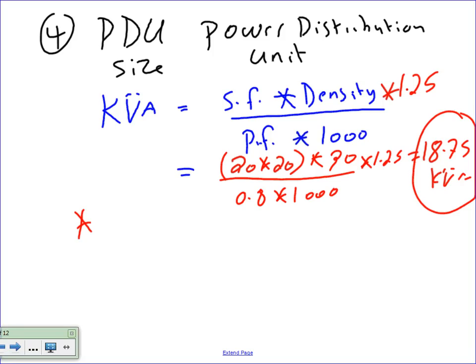Now we have 2 PDUs. These 2 PDUs will be redundant, so they will be the same size. They share the load equally, so 50% of each will be loaded, but we want to size them based on redundancy, just in case one of them goes wacko, the other will pick up the load. Okay? So we got the PDUs. Now let's size, take the 18.75 again.